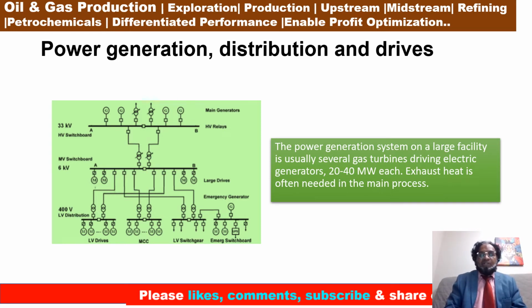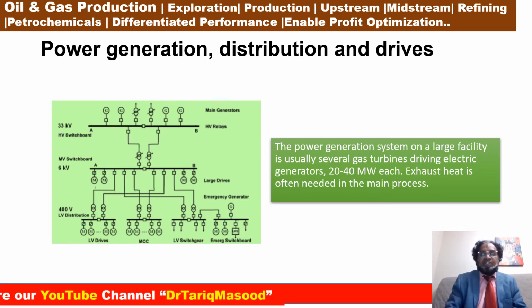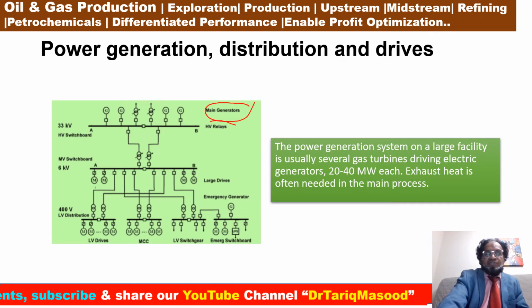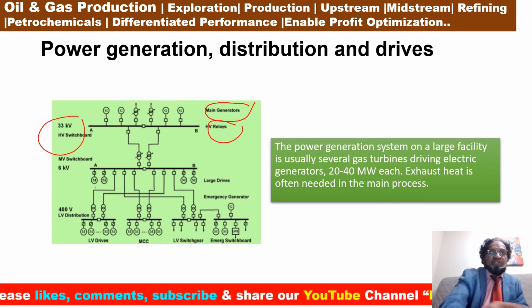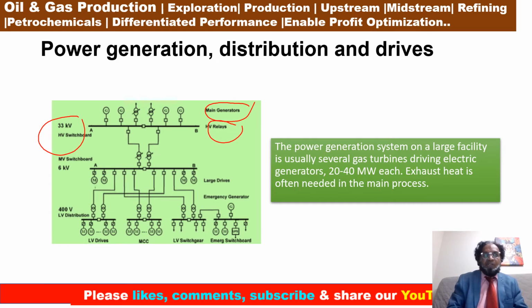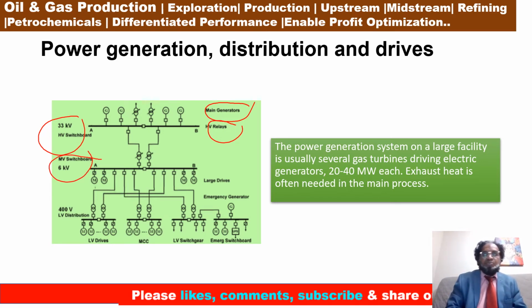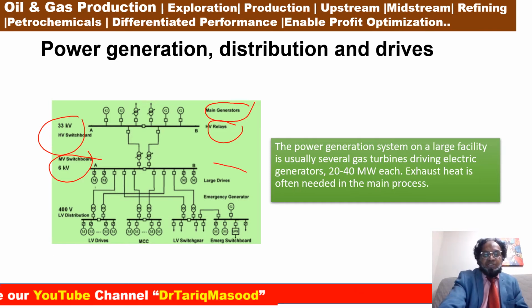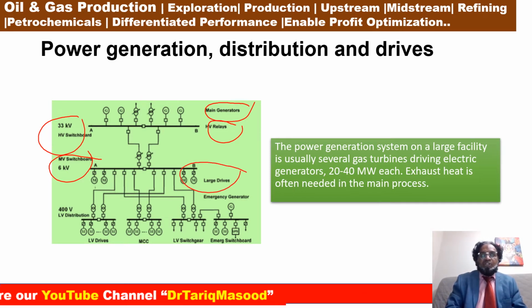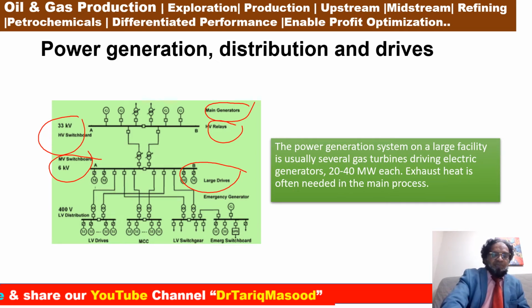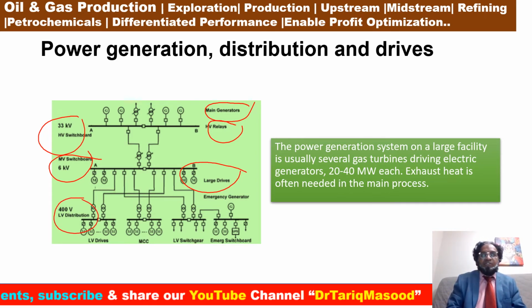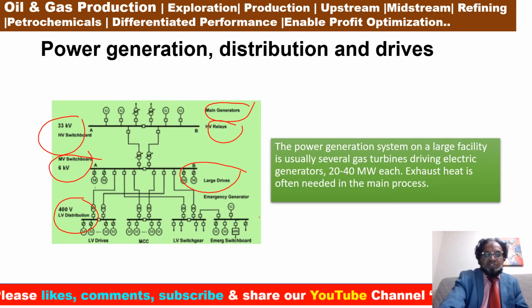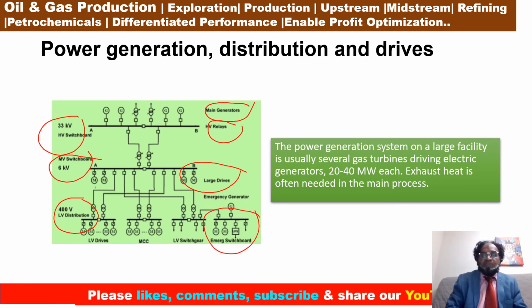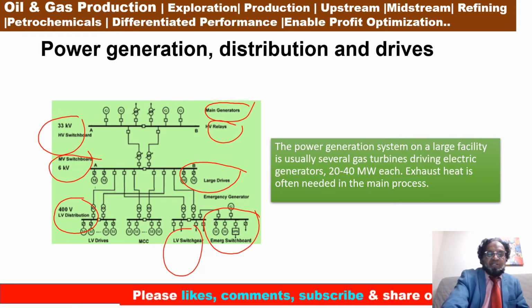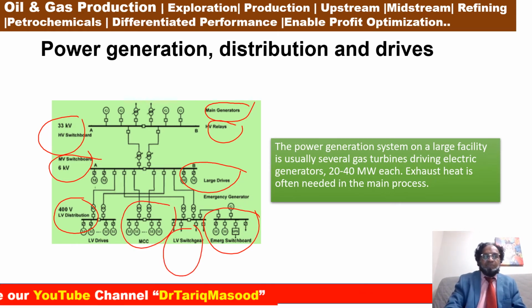Okay, electric single line diagram. If we can see here, this is my main power generators, and this is my HV relays, and over here is a 33 kV switchboard. Next over here is a 6 kV switchboard, and these demonstrate the large drives. It is further distributed over here, it is 400 volt LV distribution, and this is my emergency switchboard, LV switchgear, and this is connected with the MCC main control room.